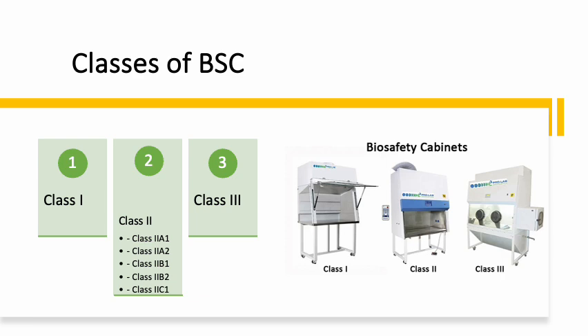Now, additionally, your Class 2 Biosafety Cabinet has different types. So, what are the different types of your Class 2 BSC? This includes your Class 2A1, Class 2A2, Class 2B1, and Class 2B2. You can also include the Class 2C1, but different manufacturers usually exclude the Class 2C1 because it is almost the same as the Type A cabinets.